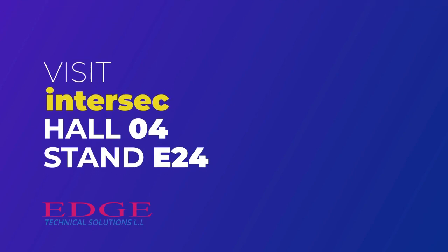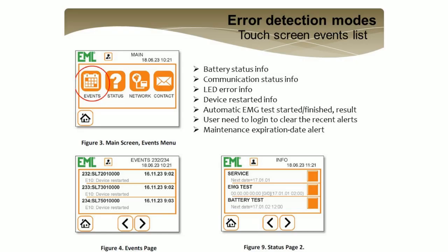It's automatic EMG test information, because you can set 2 different types of EMG tests for the system. One is for daily or weekly use. It's a short test, only 1 minute long. It tests the batteries, the LEDs, the communication, everything you need to know about the lights. And you can set a custom EMG test.